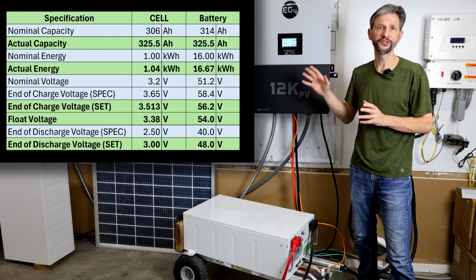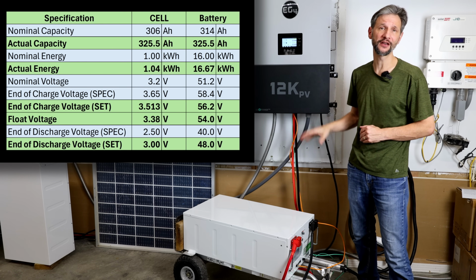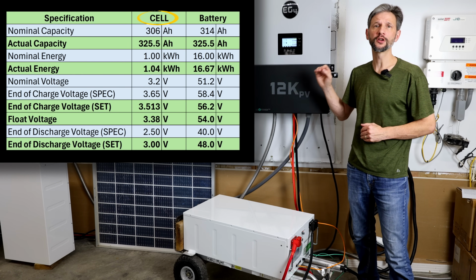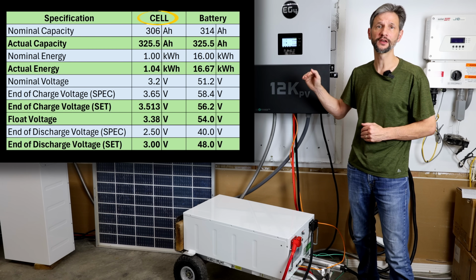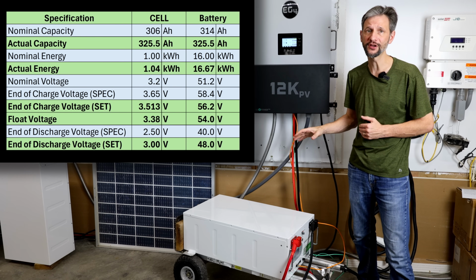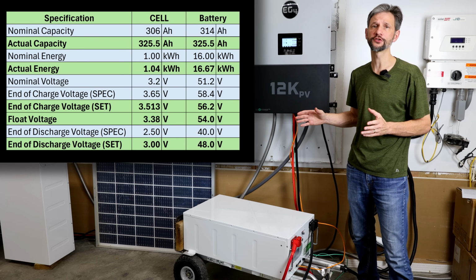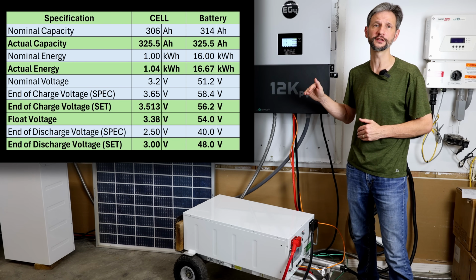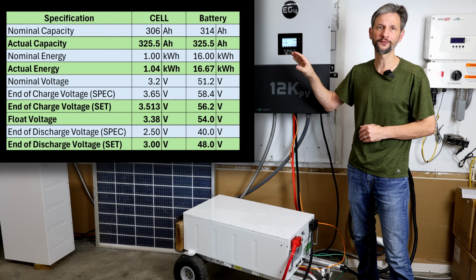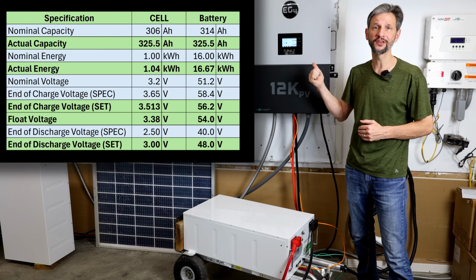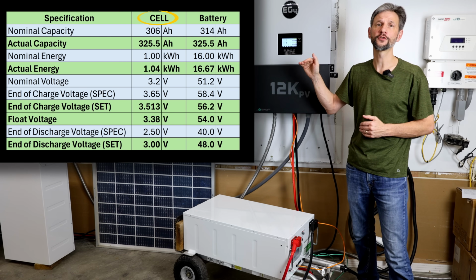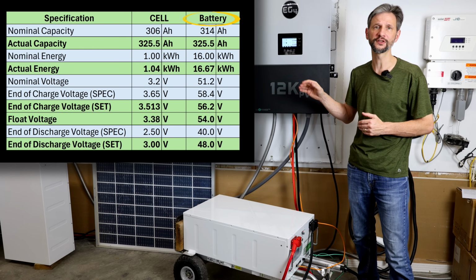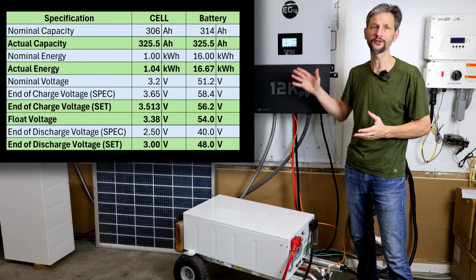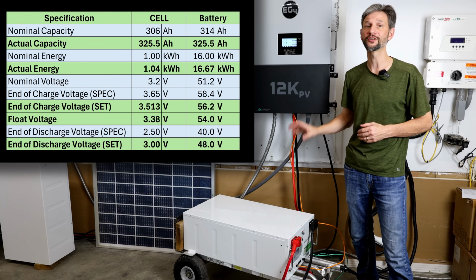Here is a chart of the voltage settings that I like to use to maximize battery life. At the battery cell level, we want to set the BMS to the cell limits because the BMS is there to protect the battery from overcharge or over-discharge without interfering with the day-to-day operation. This chart combines the battery specs for reference with my actual settings on the inverter. The cell column is the value for an individual cell, and the battery column is just the cell column times 16 for the entire assembly, since all of those cells are in series.